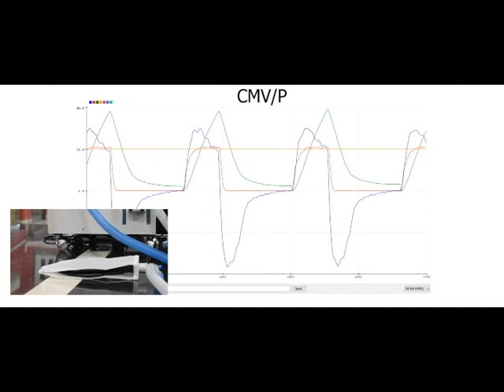Right, now here you can see that the ventilator is running in CMV-P with the settings I have just told you. You can see that all the inspiration and expiration cycles are going to the fixed pressure limit of 25 cm of water column. This red curve is perfectly stabilizing over there, and you can see the corresponding tidal volume graph, and finally the flow you can also observe in this graph.